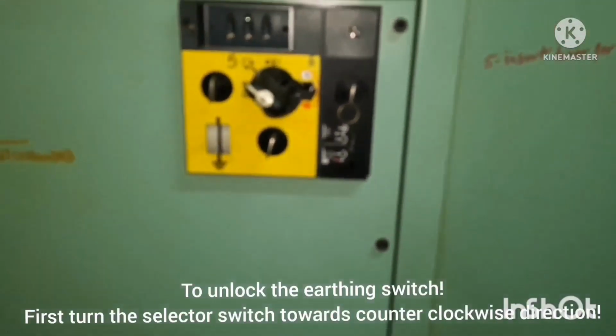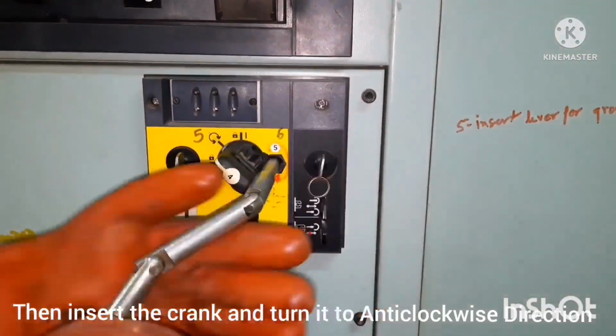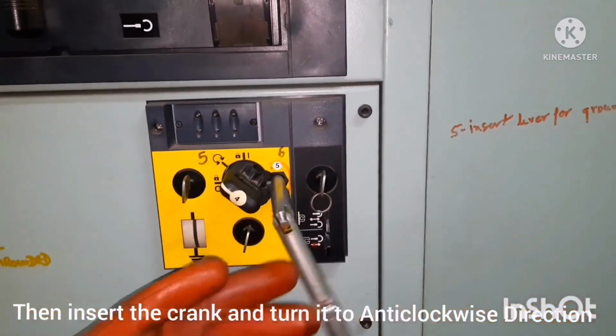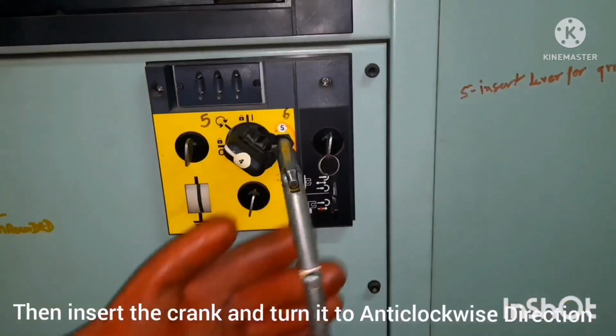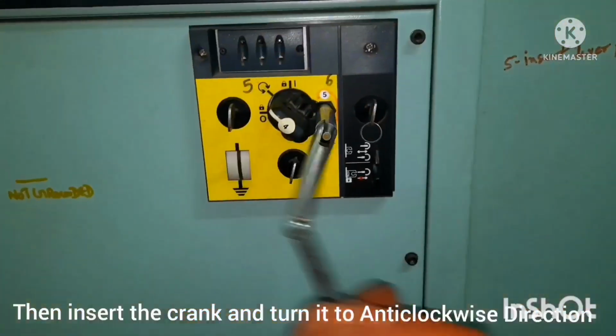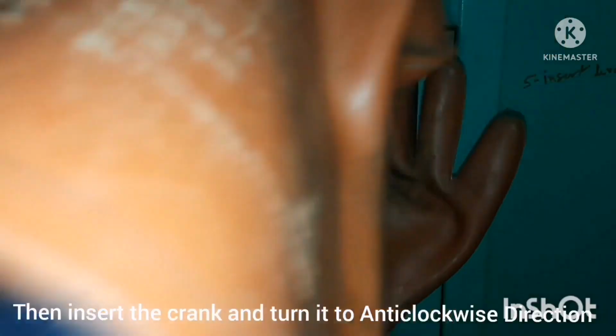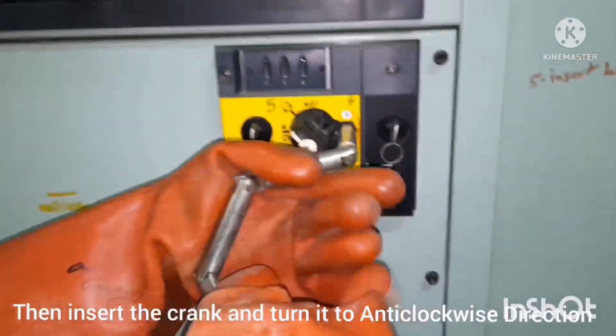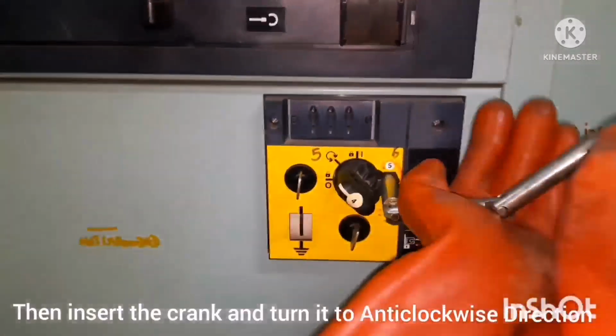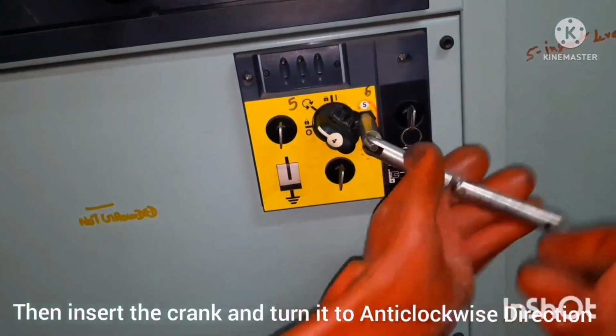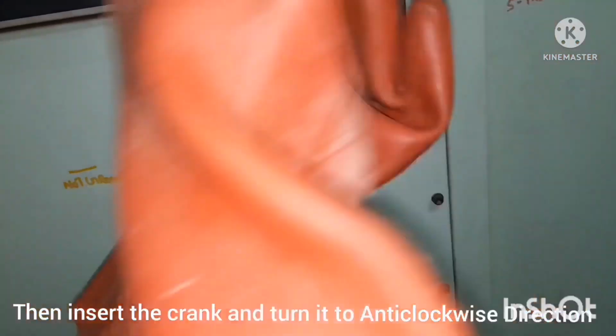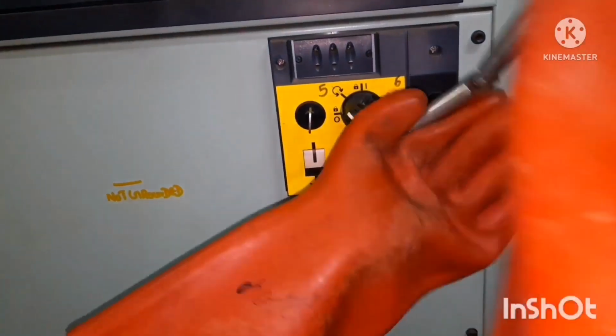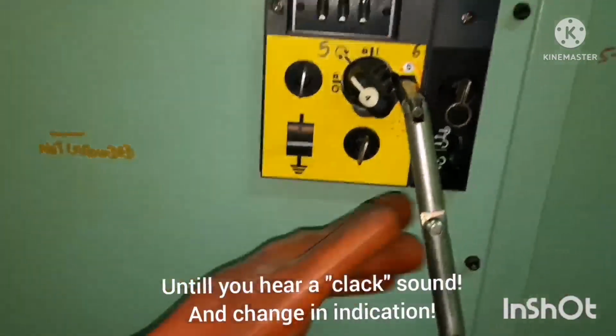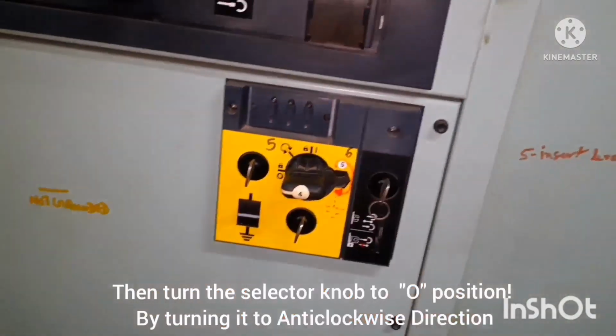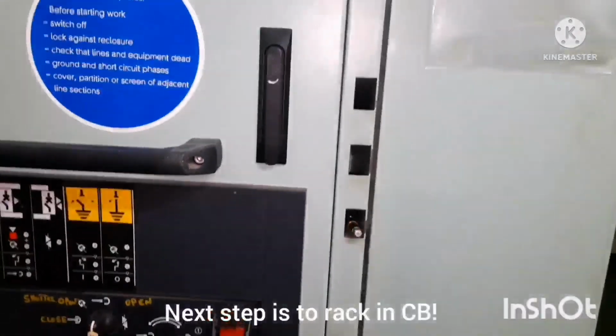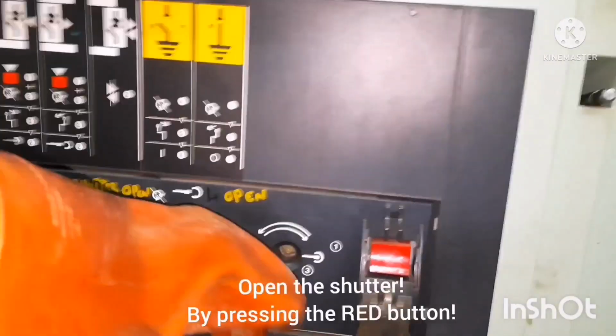Next we have to rack it. First, to unlock, you just need to insert the lever and crank it anti-clockwise. Once the cranking is done, you can see the indicator of the earthing position will change. While working on a high voltage switch box, please be very sure you're using safety gear. Now you can hear the click sound, and turn the knob to the O position. Everything is done.